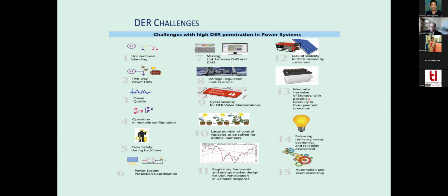Storage is getting its way more and more into the system, and how do we maximize the value and use it as a flexible operation—especially because battery is probably one of the most flexible devices, as it can operate in 4-quadrant operation. If you take P and Q, this is positive P and positive Q, this is positive P and negative Q, here is negative P and negative Q, which is like charging through discharging, and the other one is negative P and positive Q. So the electronics, if designed well, provide a lot of flexibility.